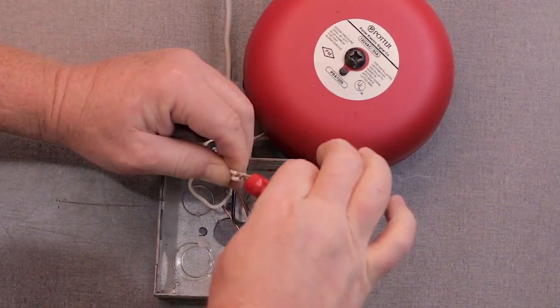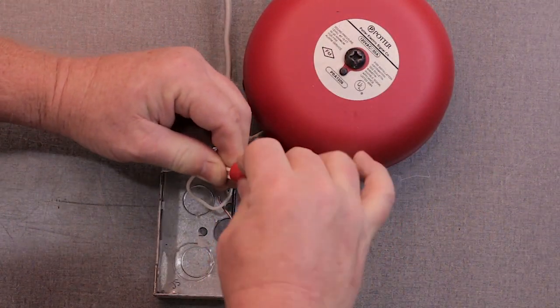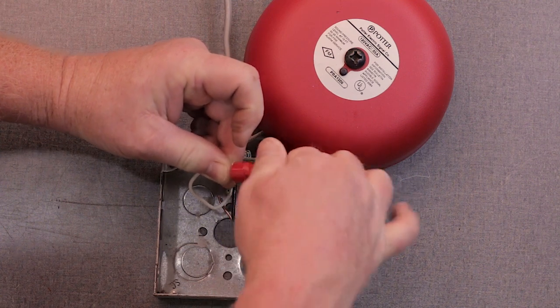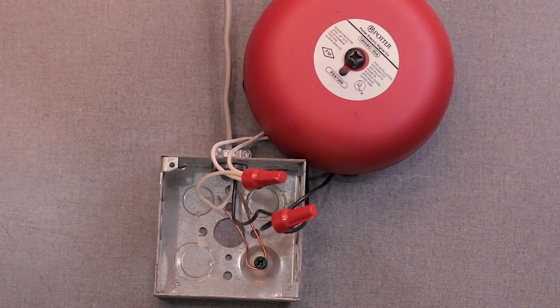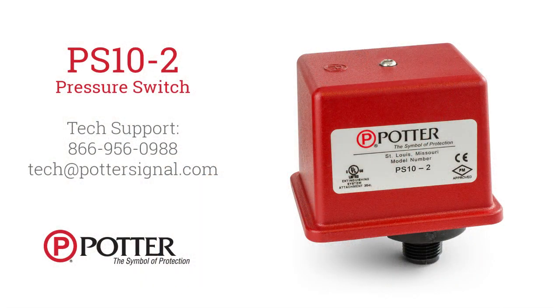When the pressure switch activates, the common and normally open terminals will close. This will switch the hot wire that is on the common terminal out through the normally open contact. If you have further questions about any of our products, please contact our tech support team by calling 866-956-0988 or emailing tech at pottersignal.com.